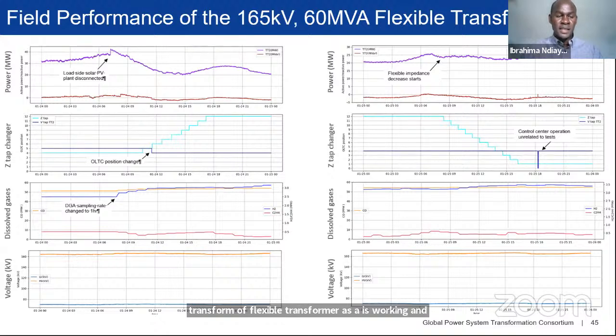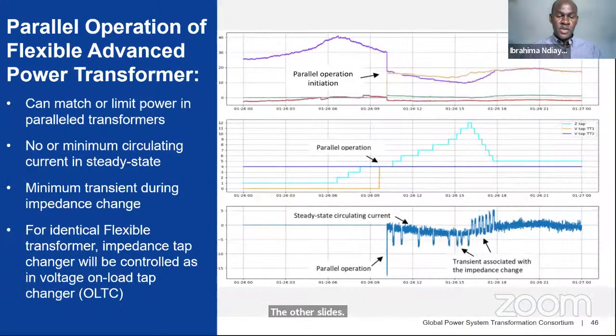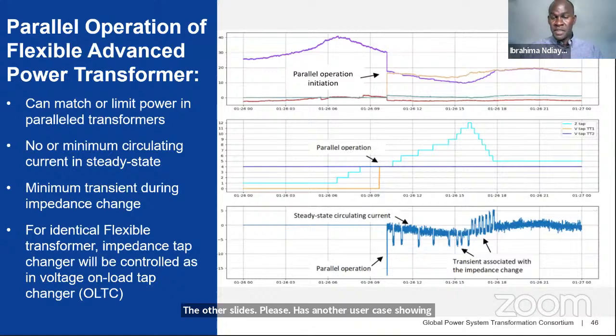The next slide has another use case showing the same transformer when it is operating in parallel with a similarly sized transformer. You can see that at the point of parallelizing the two transformers, the original flexible transformer was taking the full power. As soon as the second transformer is put in parallel, they were sharing the load. At the beginning, the load was not perfectly shared, but when we match the impedance, you can see the two transformers are now sharing the load exactly.